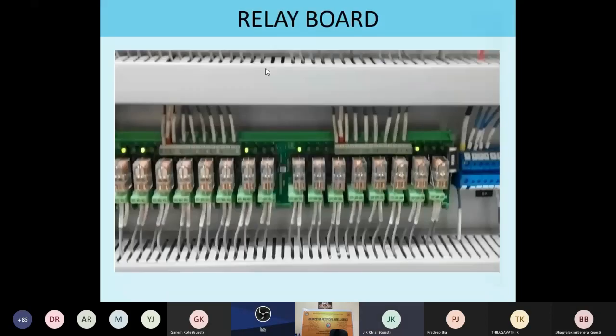The field signal is coming to the control room by means of wire. In the control room, there are some fuses protecting the PLC card. So if there is any short circuit inside the field, then the spurious noise or voltage cannot reach the PLC input card. So for protection purposes, we have connected a fuse to the terminal box inside the control room or any place. Then to the relay board. Then the signal is coming to the relay board.